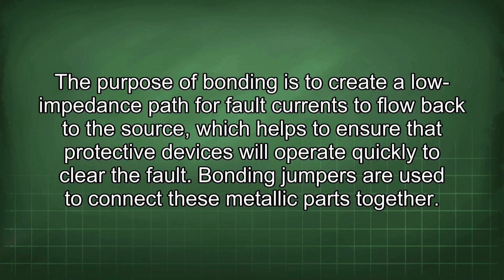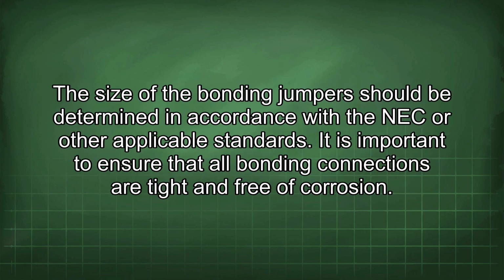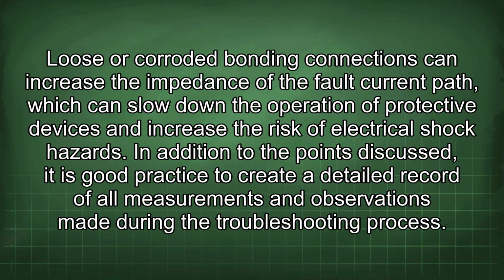Bonding jumpers are used to connect these metallic parts together. The size of the bonding jumpers should be determined in accordance with the NEC or other applicable standards. It is important to ensure that all bonding connections are tight and free of corrosion. Loose or corroded bonding connections can increase the impedance of the fault current path, which can slow down the operation of protective devices and increase the risk of electrical shock hazards.